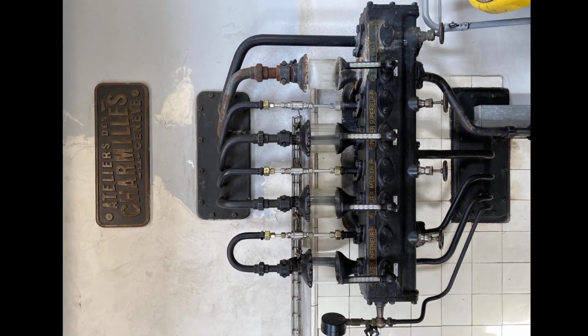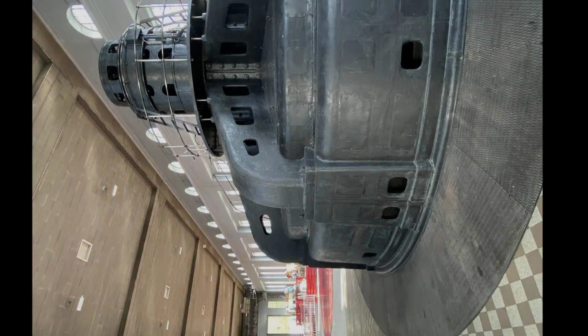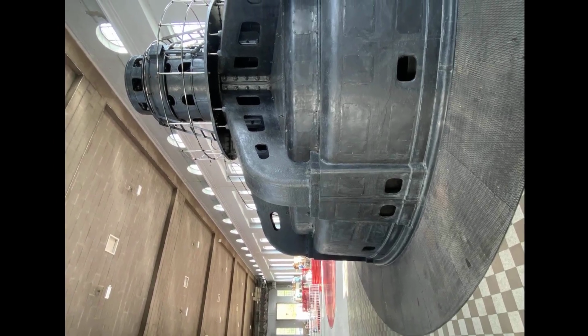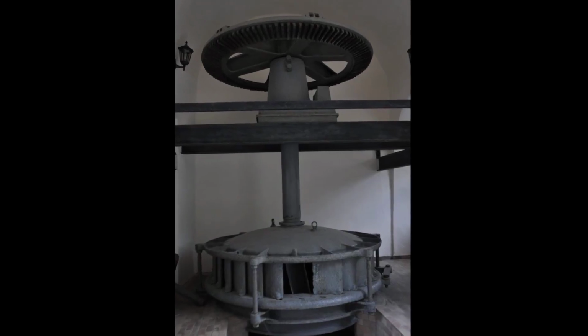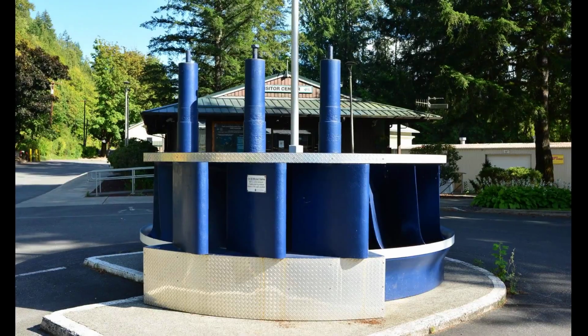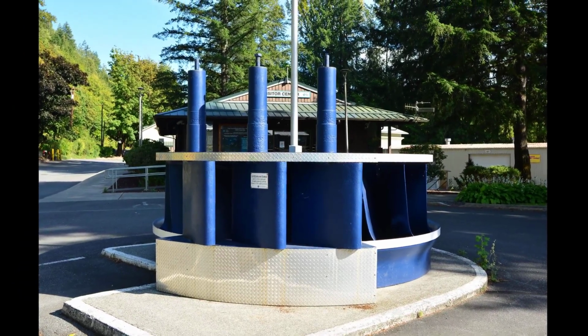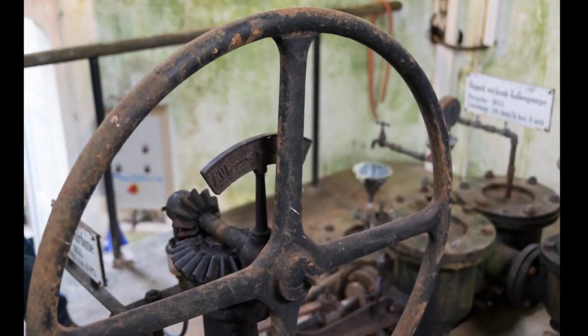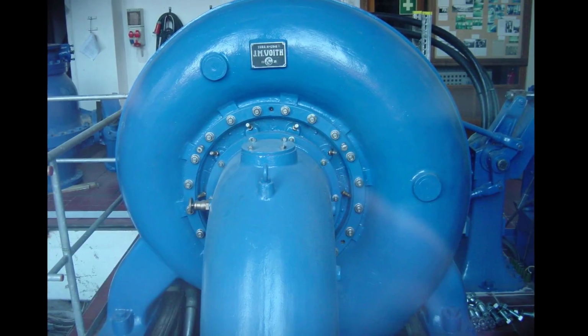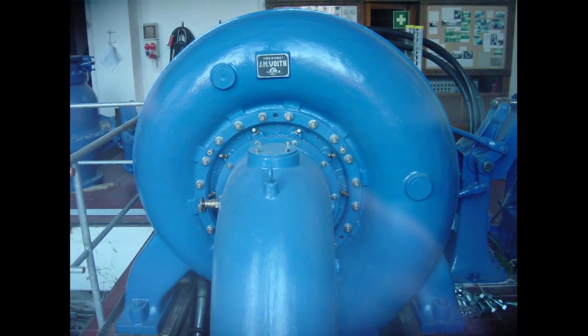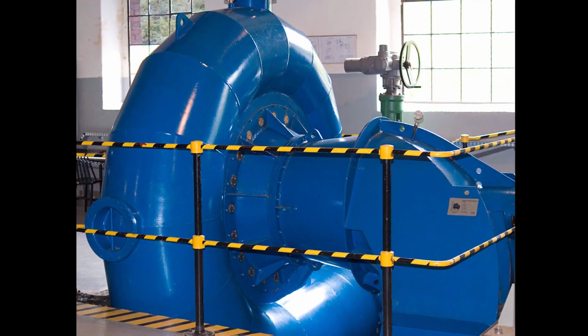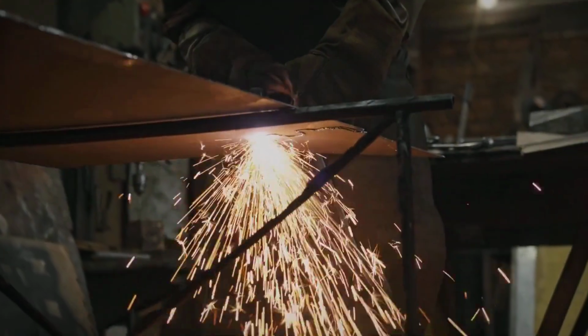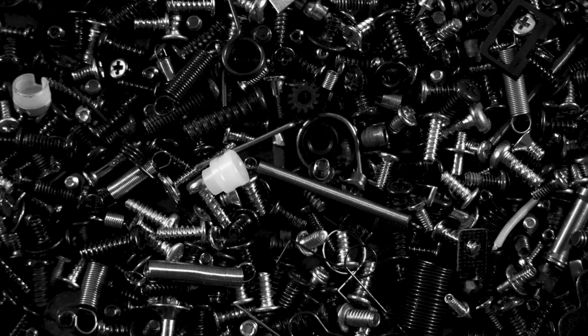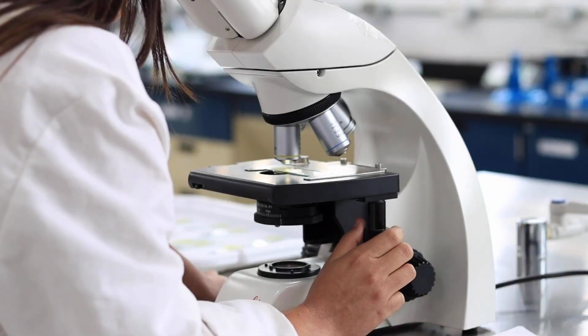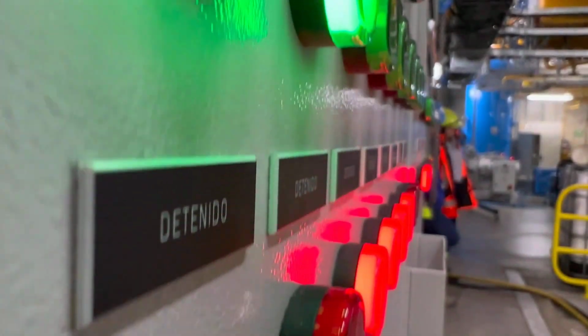Each unit is a Francis turbine, a steel runner nearly 7 meters across, sitting at the bottom of a shaft, with water arriving around it through a spiral case and leaving downwards through a draft tube. The rotating assembly, runner, shaft, and generator rotor, weighs 920 tons. That is roughly 2 fully loaded jumbo jets, spinning 2.5 times a second, 1 floor below where people walk. And the only thing separating that spinning mass from the full pressure of the reservoir is a steel lid called the head cover. It is bolted down. Remember that word.